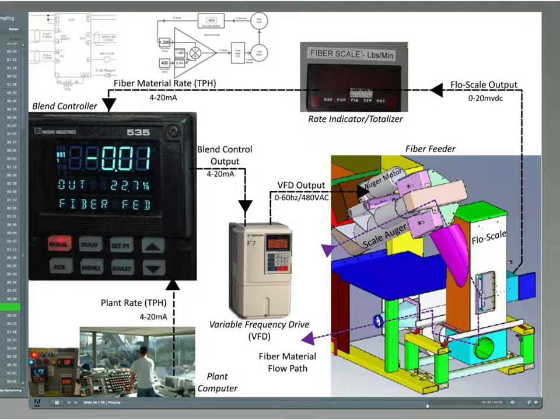Digital output 2. Alarm relay on to sound scale plugged horn. If the material, fiber, being weighed plugs up in the scale for some reason, the auger packs material in and the Flo-Scale reading begins to increase rapidly. This may have been caused by the scale being overfed or the discharge airstream through the blower was not flowing when material was being fed.